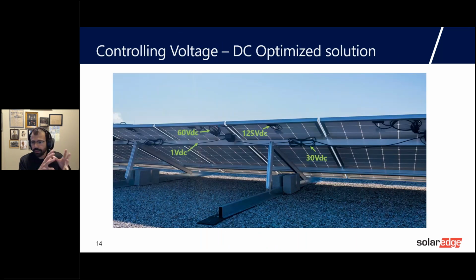So what does that mean? I'm showing here a quick picture of the array and the voltage levels. As soon as there is a rapid shutdown event, the majority of the voltage levels in the array are going to be at 30 volts DC or less. The string level output is going to be 30 volts DC, and the output of the optimizer is 1 volt DC. Like I mentioned, you still have 125 volts DC at the combination of 2 panels. So that's the maximum voltage that will be seen in the array.